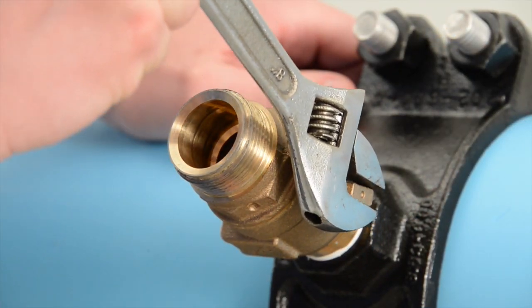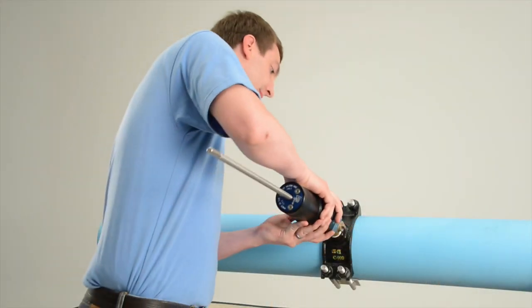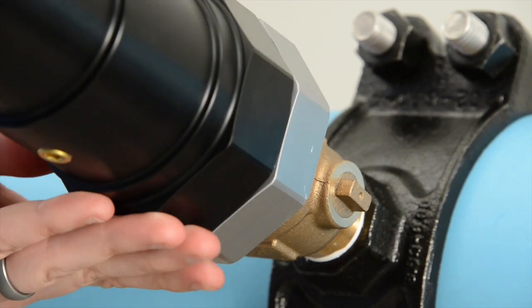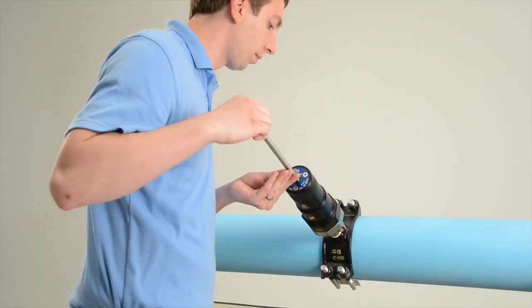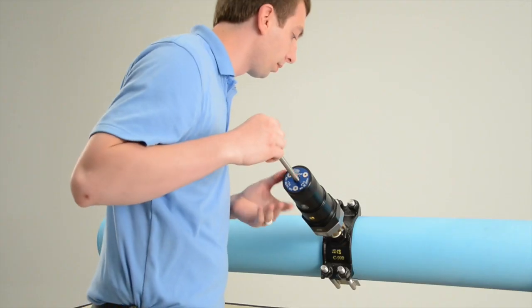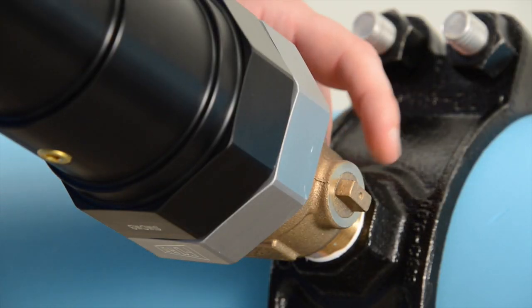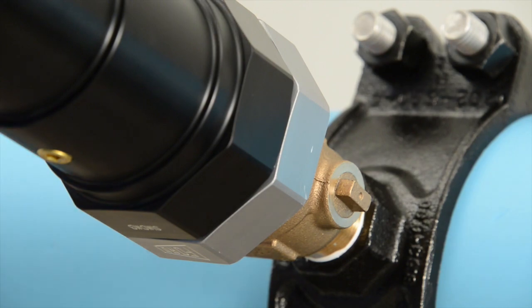Open the valve. Hand tighten the SimTap onto the corporation stop. Gently push the shaft through the open valve until the pilot bit makes contact with the pipe. It is important to check that the valve is fully open to prevent any unnecessary damage to the valve or the SimTap.